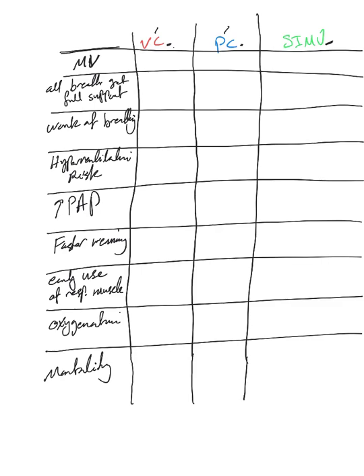This comparison can be tricky, but let's start with minute ventilation. A minimum minute ventilation is guaranteed in volume control. It is not guaranteed in pressure control because the tidal volume is variable from breath to breath, depending on the mechanics of that breath based on the pressure target. With volume control, you can set the minimum amount of minute ventilation or tidal volume you need.